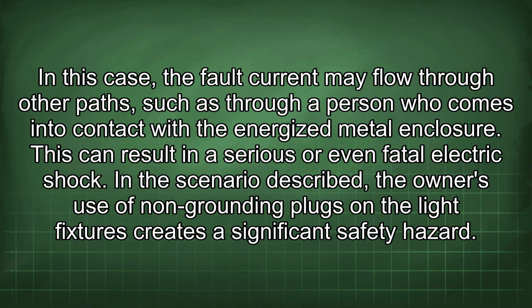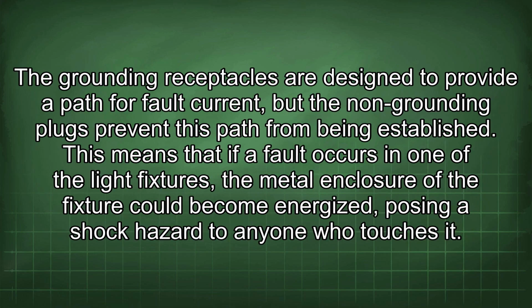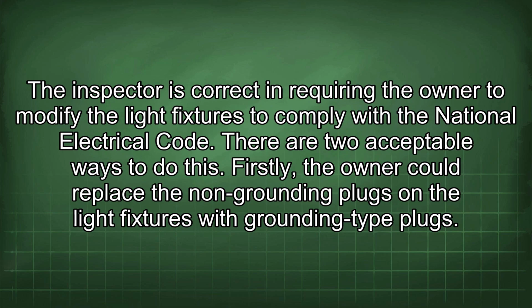In the scenario described, the owner's use of non-grounding plugs on the light fixtures creates a significant safety hazard. The grounding receptacles are designed to provide a path for fault current, but the non-grounding plugs prevent this path from being established. This means that if a fault occurs in one of the light fixtures, the metal enclosure of the fixture could become energized, posing a shock hazard to anyone who touches it. The inspector is correct in requiring the owner to modify the light fixtures to comply with the National Electrical Code.